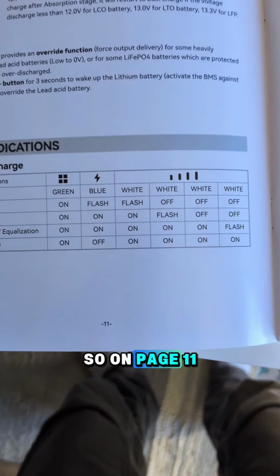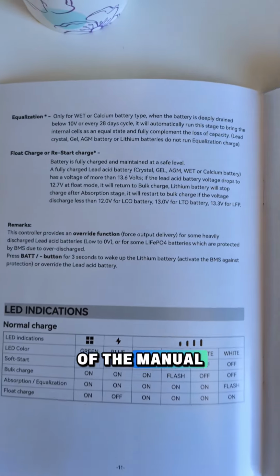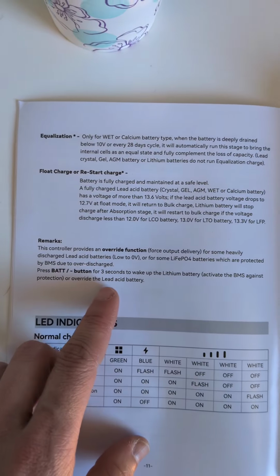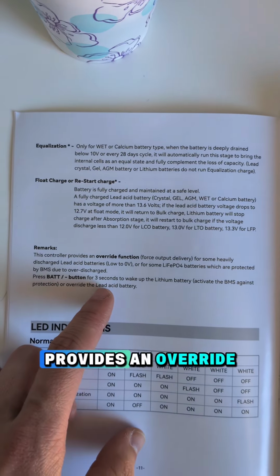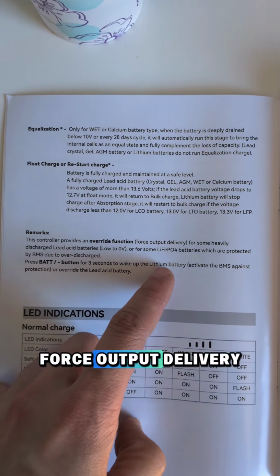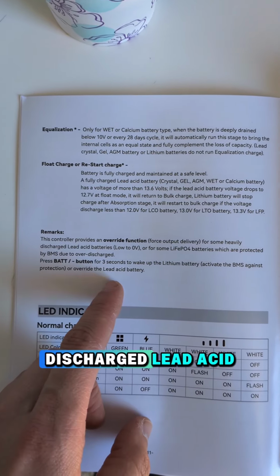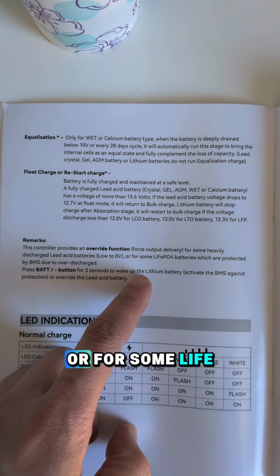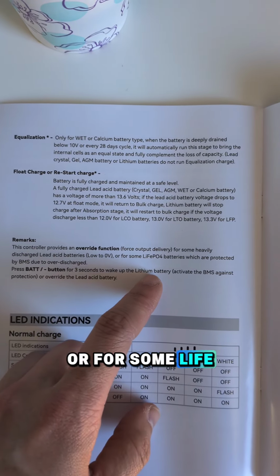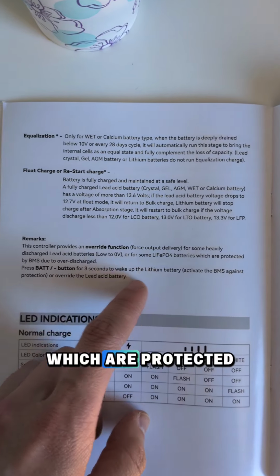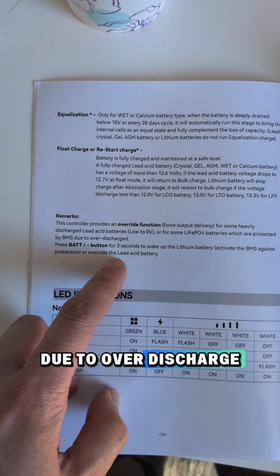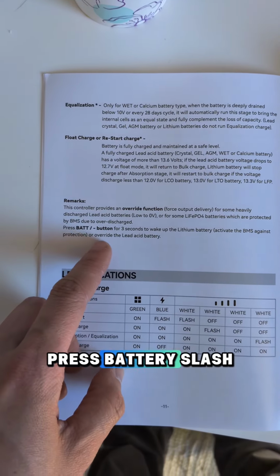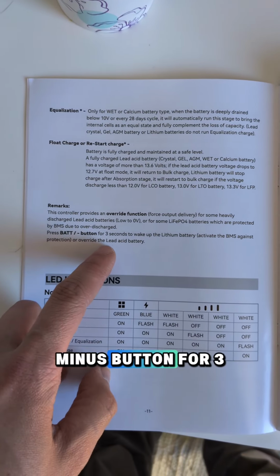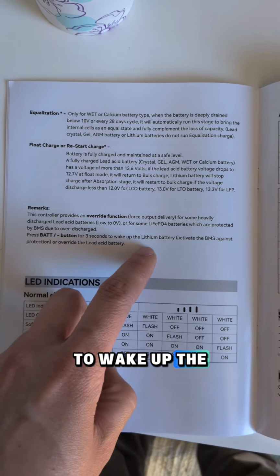So on page 11 of the manual, under the remarks, it says this controller provides an override function, force output delivery, for some heavily discharged lead acid batteries or for some LiFePO4 batteries which are protected by the BMS due to over discharge. Press the battery slash minus button for 3 seconds to wake up the lithium battery.